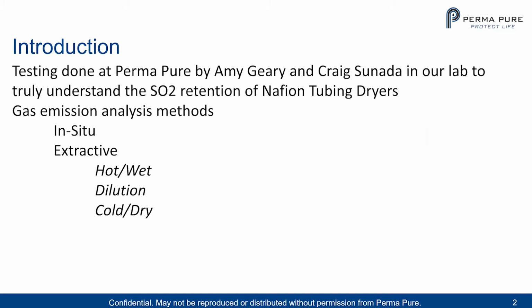Just to begin, there's a couple of different gas emissions analysis methods. There's in situ, where you actually have the analyzer and the sample extraction directly on the stack, and you're measuring the sample right there on a hot and wet basis. There's also extractive methods where you're pulling out the sample and then you're bringing it to the analyzer in a shed someplace. Those can either be done hot and wet. That means you're taking the sample and putting it through a heated line, and you're measuring it in a hot and wet method. There's also dilution, where you can dilute and analyze that.